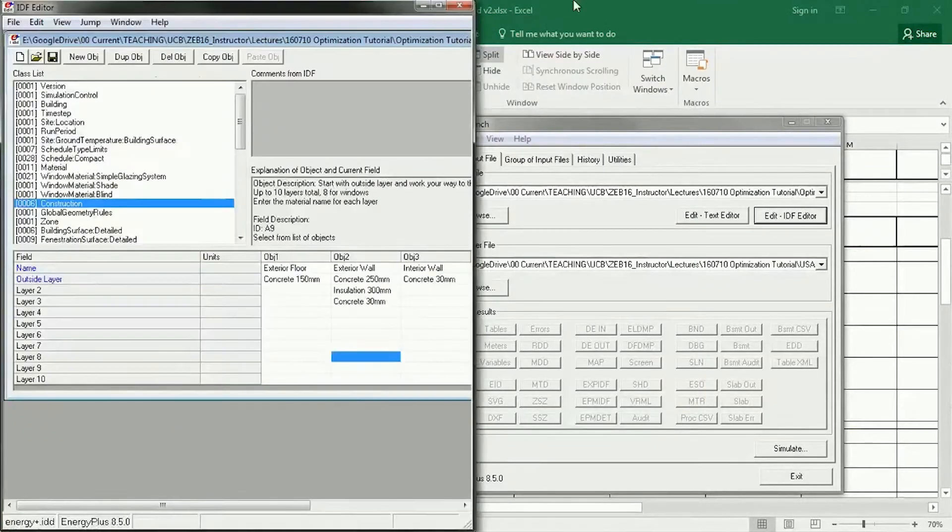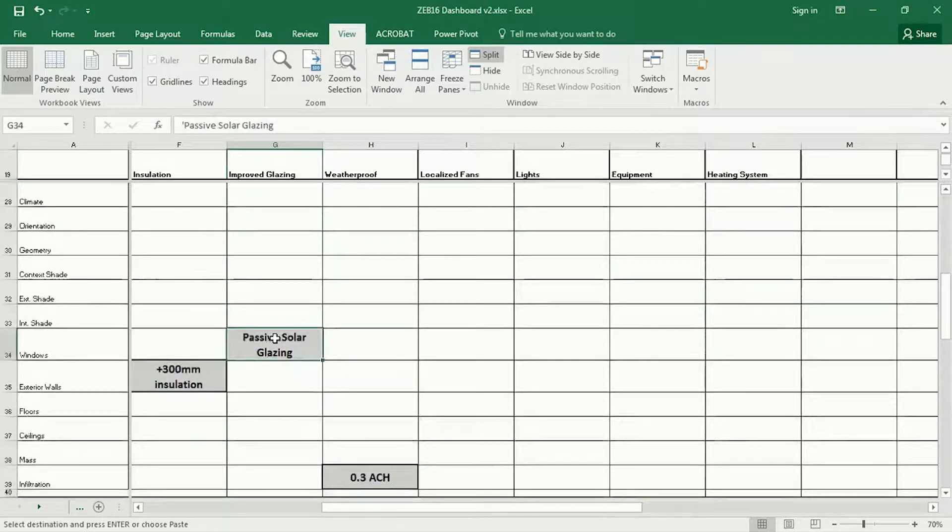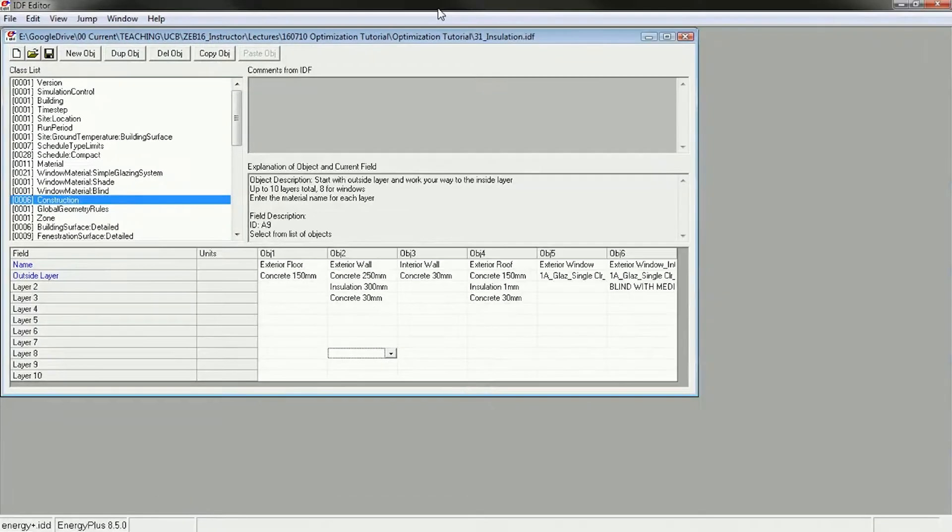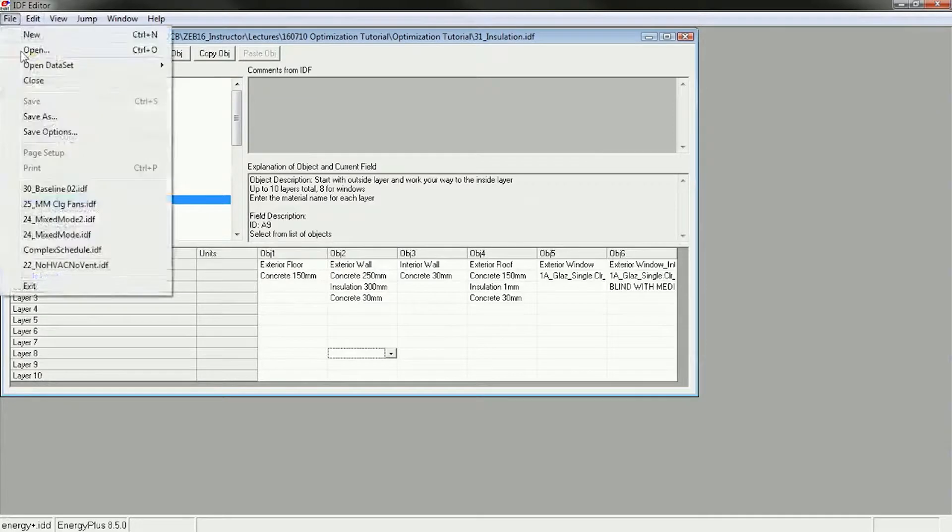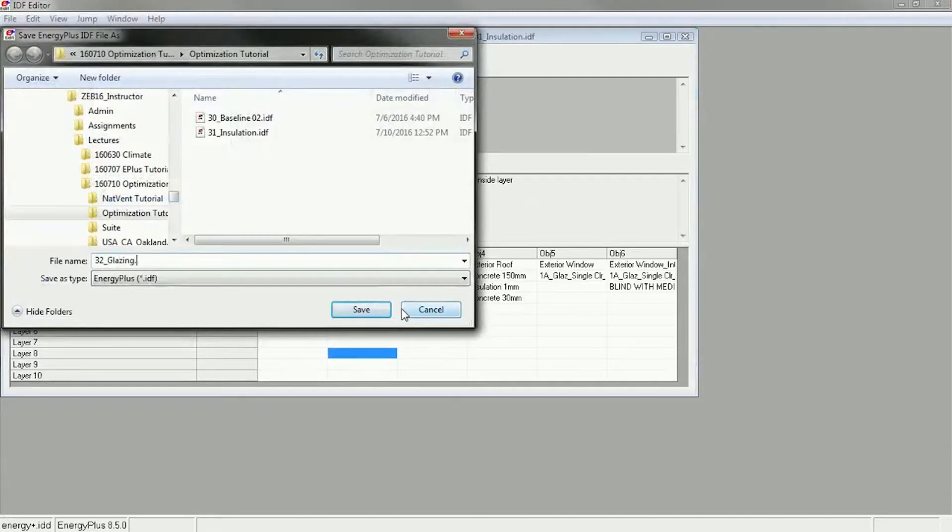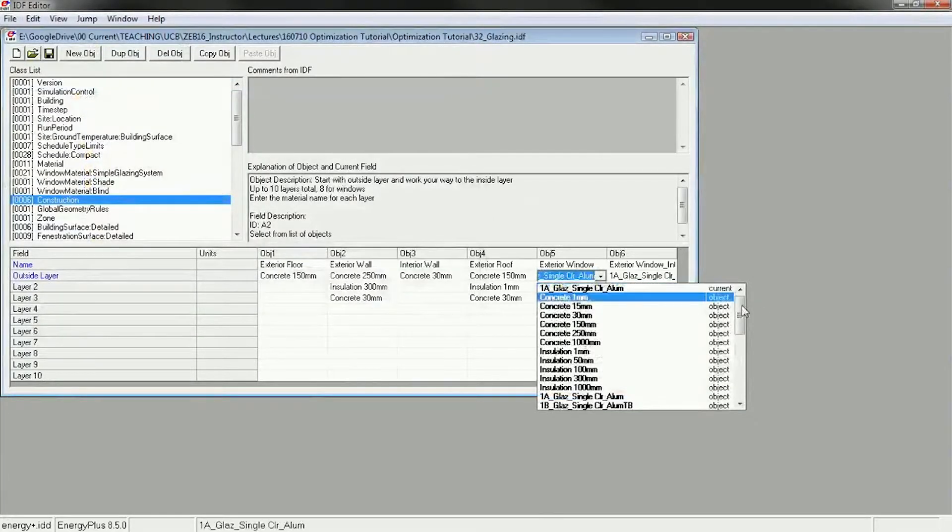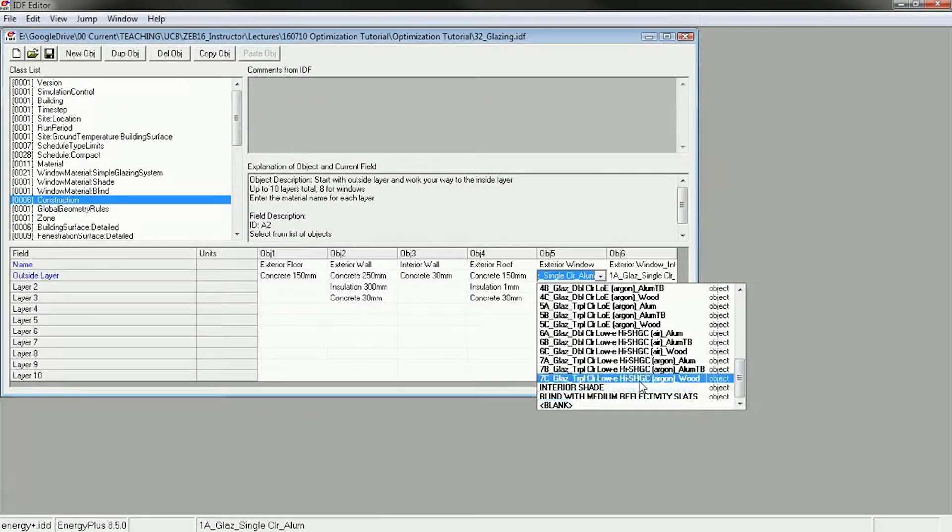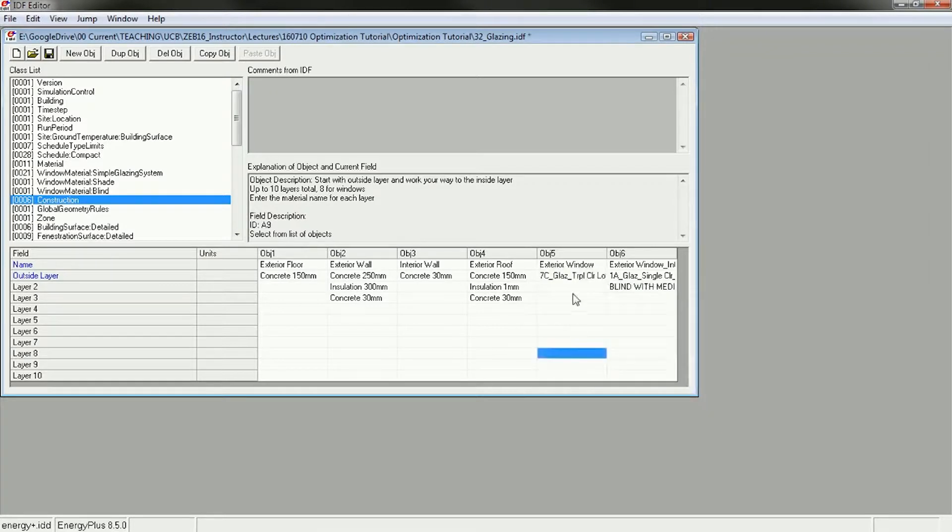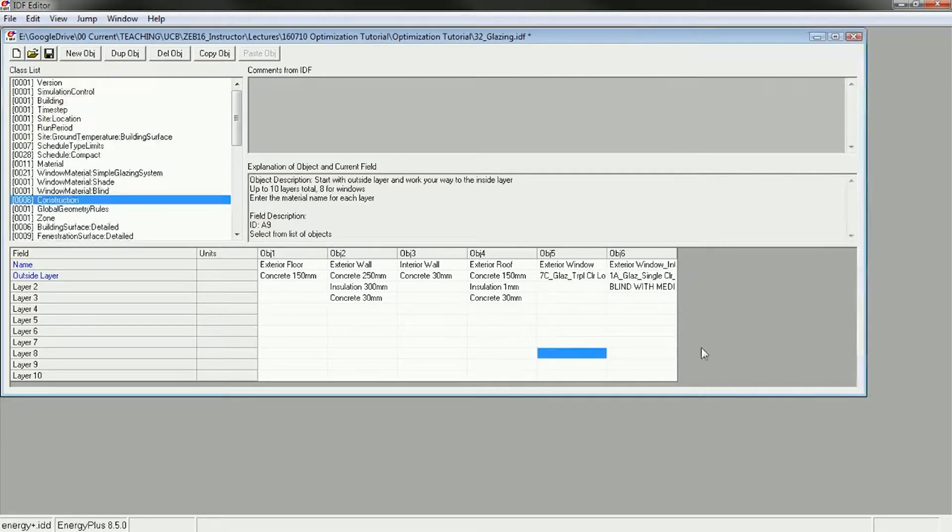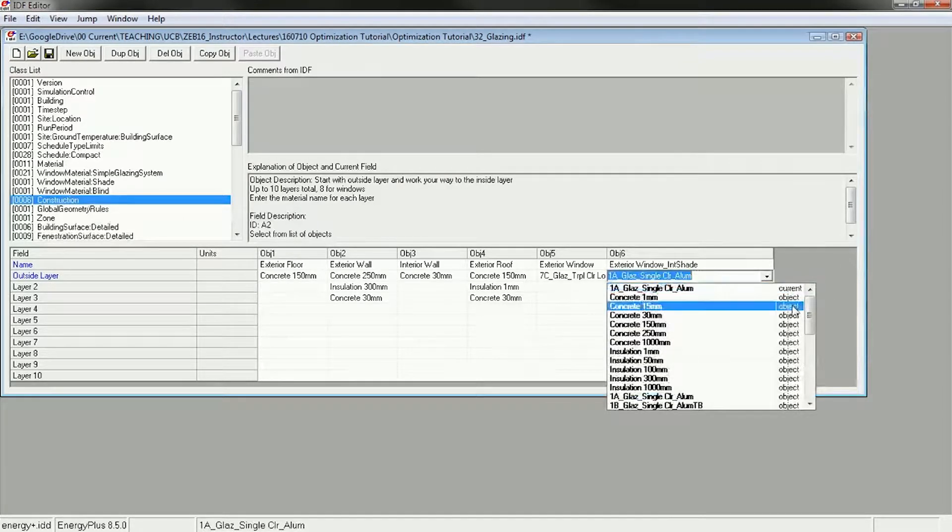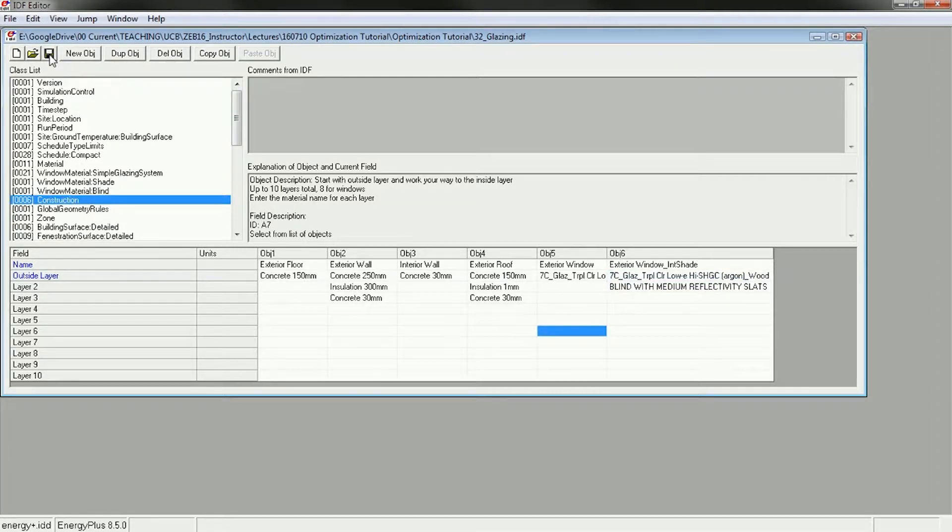The next improvement I've got is improved glazing. So I'm going to switch to the passive solar glazing here which is in the constructions again. I'm going to save this as 32 glazing and I'm going to change the glazing to, I'm going to use a really good one here, triple clear low E high solar heat gain coefficient. So that should be a low U value and high SHGC. And then I'm also going to change my blinds here to do the same thing. I'm going to save that.